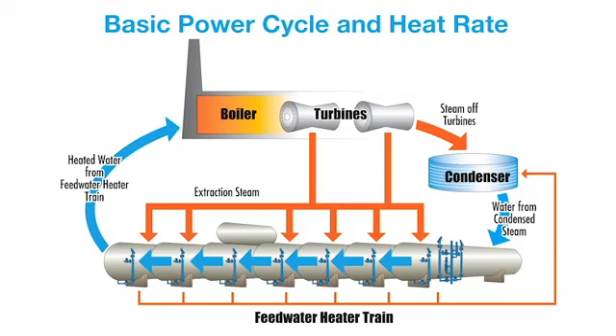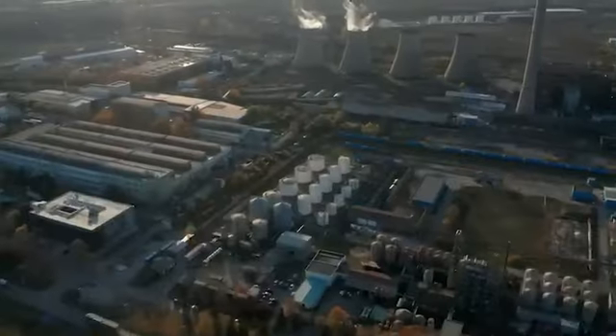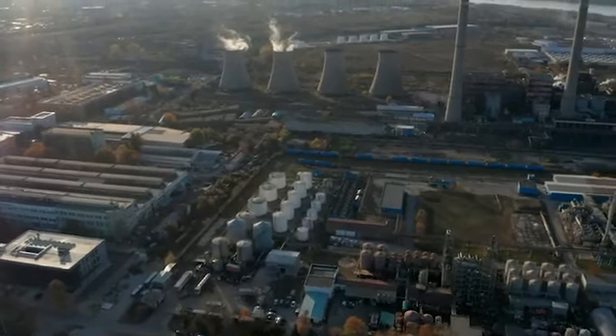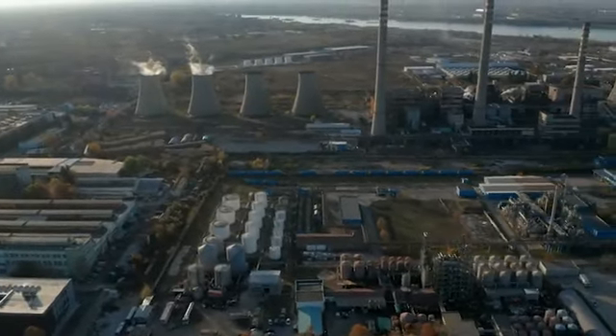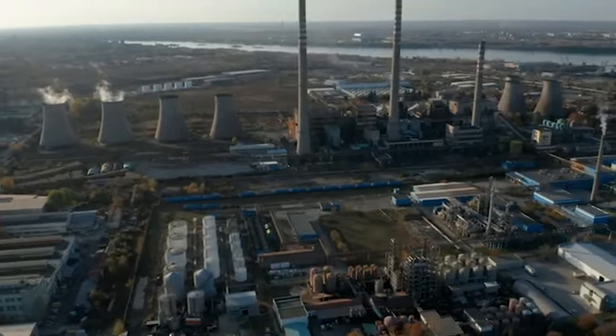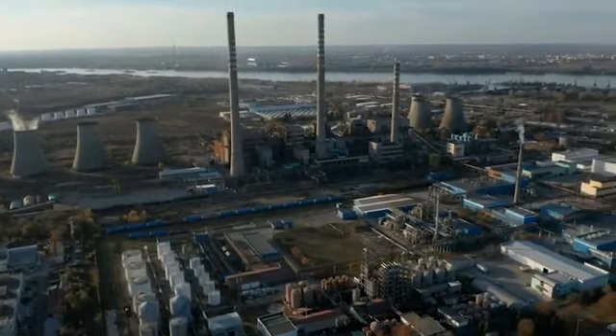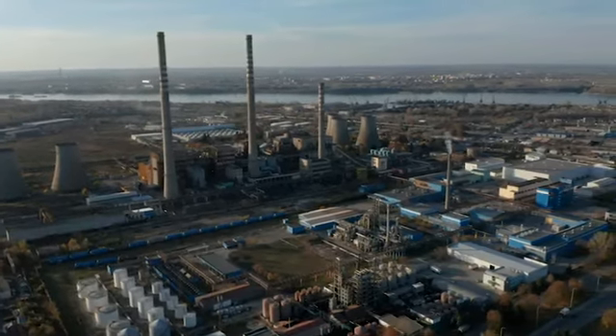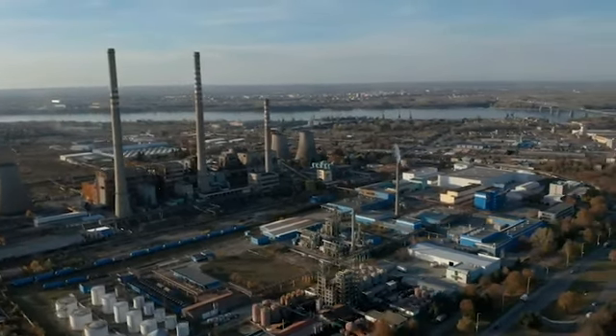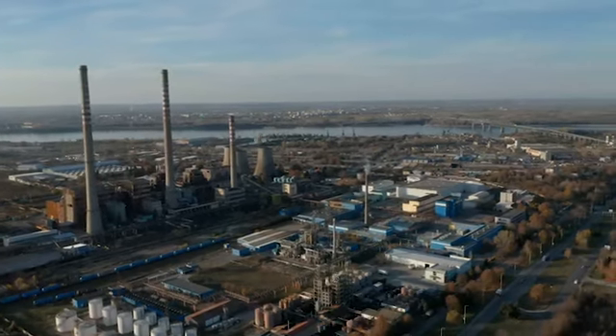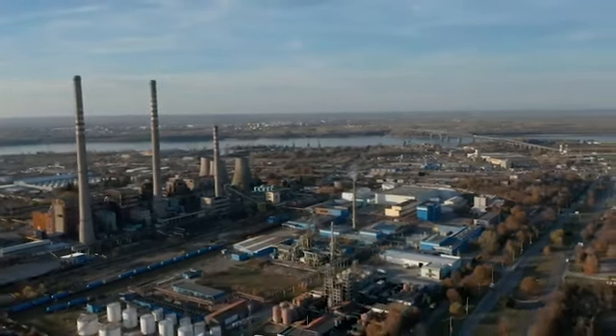Although a reduction in fuel costs through improved feed water heater level control has the most significant impact on a company's bottom line and their ability to compete in unregulated energy markets, the benefits go far beyond consumption and cost. For instance, a plant can realize a quantifiable reduction in CO2 and other emissions simply by improving feed water heater level control. Additionally, extended boiler longevity by eliminating overfiring to overcome shortfalls in final feed water heater temperature is also achievable. And of course, there is the public relations value in that a plant is pursuing all avenues to minimize negative impact on the local community and environment.